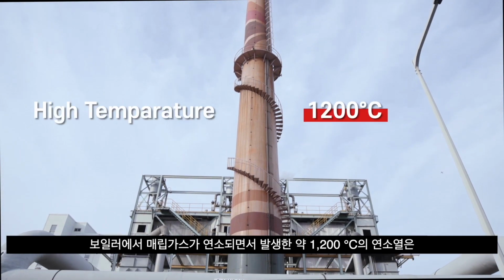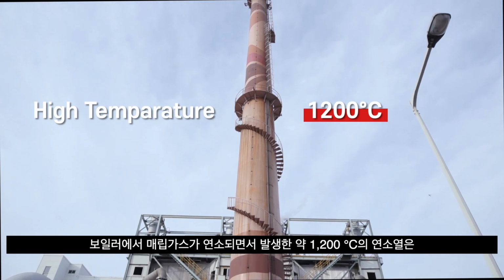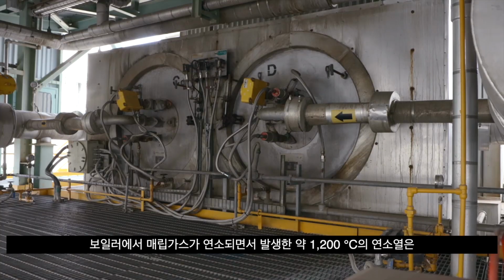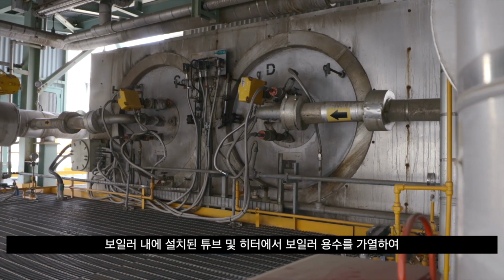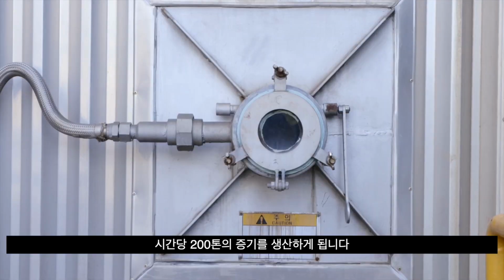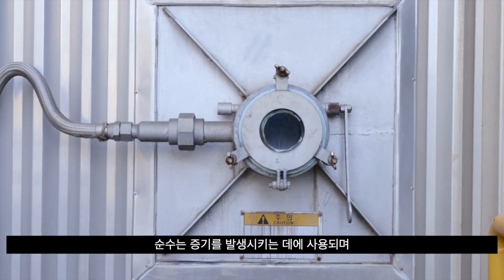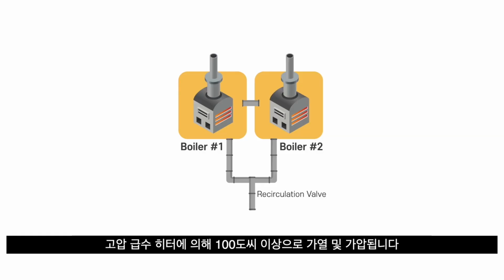The combustion of landfill gas generates a very high temperature of 1,200 degrees Celsius, which is used to heat water that produces 200 tons of steam per hour. Pure water is used for generating steam, and this is pressurized and superheated above 100 degrees Celsius by a high-pressure feed-water heater.